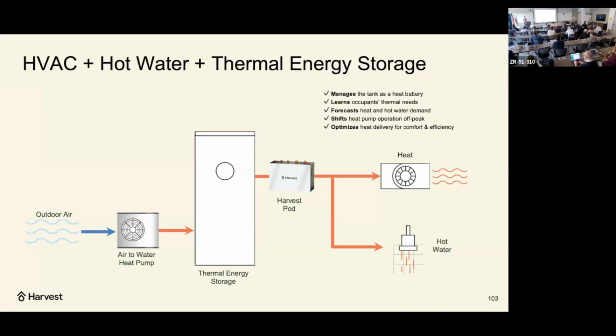The second is to use one single very high performance heat pump, a CO2 heat pump in this case, to do both heating and hot water and address both end uses, making that heat pump provide both heating and hot water flexibly with that architecture.